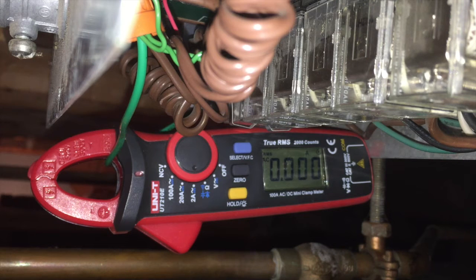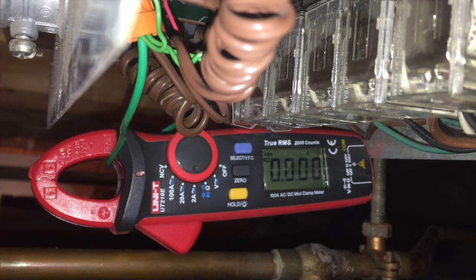Bearing in mind that this is counting the power coming in through the 24 volt supply line to the thermostat. Most of what's powering the thermostat itself goes back through this common wire. But if it's actually turning on the heat for a zone, then that's going to be energizing the relay coil on that zone, and that's going back through the white wire. So that's not going to be captured in this. It's taking a different return path. But I'm assuming that's also current that's accounted for in the 100 milliamps they're saying the board itself uses, because it's energizing the relays on the board.